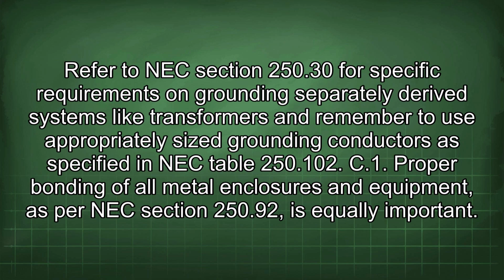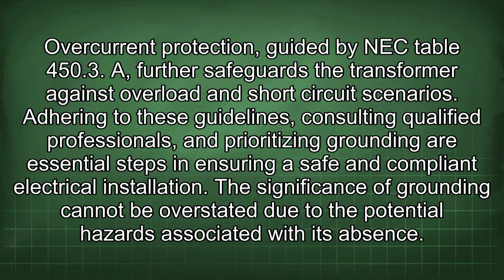Refer to NEC section 250.30 for specific requirements on grounding separately derived systems like transformers, and remember to use appropriately sized grounding conductors as specified in NEC table 250.102(C)(1). Proper bonding of all metal enclosures and equipment, as per NEC section 250.92, is equally important. Overcurrent protection, guided by NEC table 450.3(A), further safeguards the transformer against overload and short circuit scenarios. Adhering to these guidelines, consulting qualified professionals, and prioritizing grounding are essential steps in ensuring a safe and compliant electrical installation. The significance of grounding cannot be overstated due to the potential hazards associated with its absence.